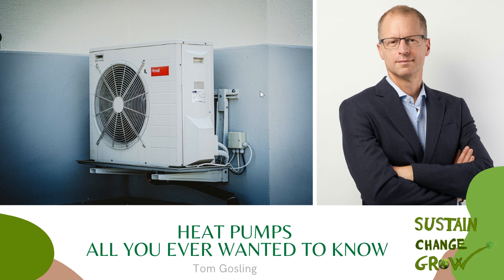And as we gain in experience, and with recent technology improvements in heat pump design, efficiency has dramatically improved. There have been some heat pump studies done by the UK government looking at efficiency of installed heat pumps, and they find a wide variation. They find an average efficiency of about 2.8 units of heat for every unit of electricity. But with the improvement in heat pump technology, I think that's going to rapidly move the average well above 3. So this problem about high bills is only going to arise when you have genuinely very poor installations.